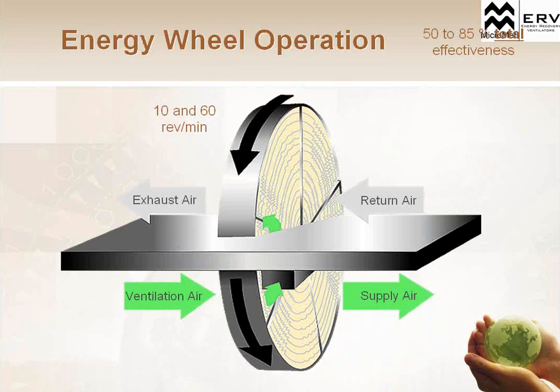We talked about a wheel being a typical application in the commercial marketplace. An energy recovery wheel is going to spin between both of those airflows. It spins between the return air that passes through the wheel. It picks up the energy in the wheel and spins into the other airflow, where that ventilation air is going to come in, pick up that energy, and go into the building.